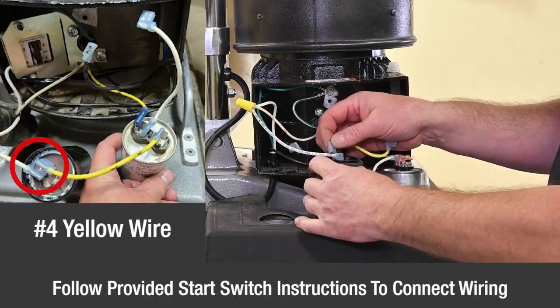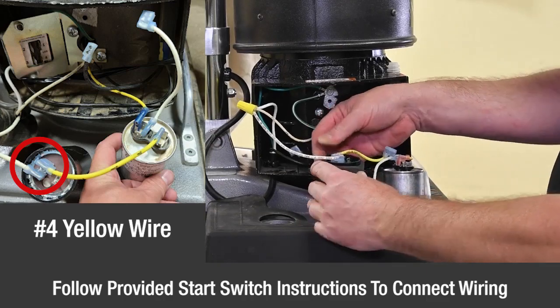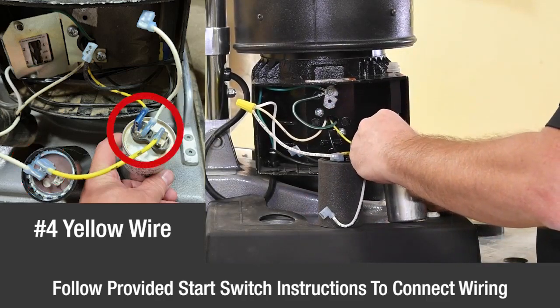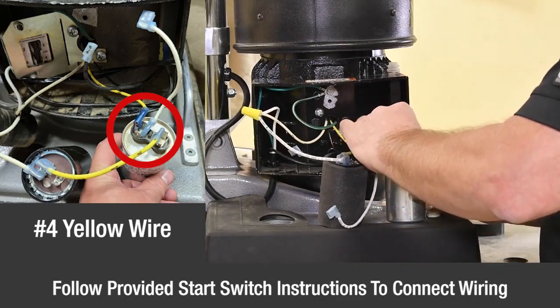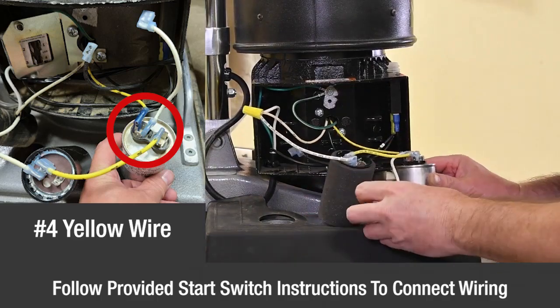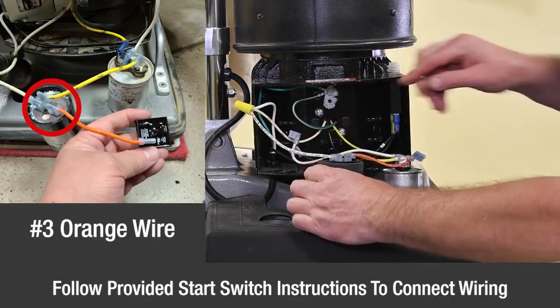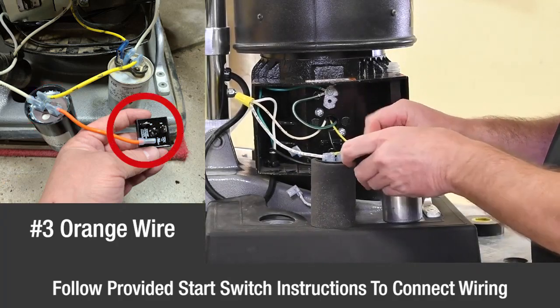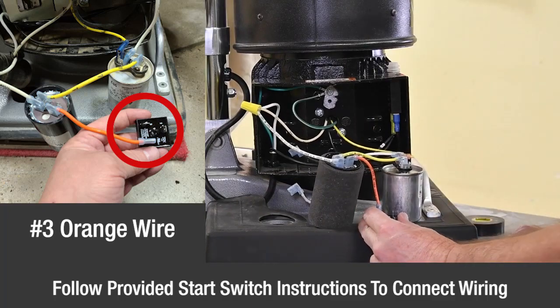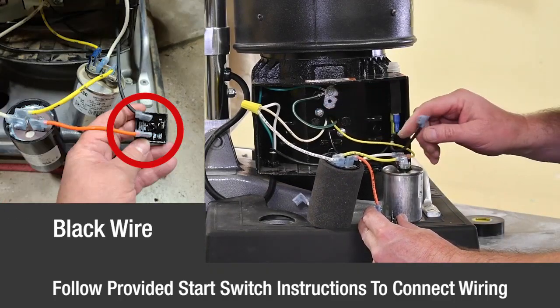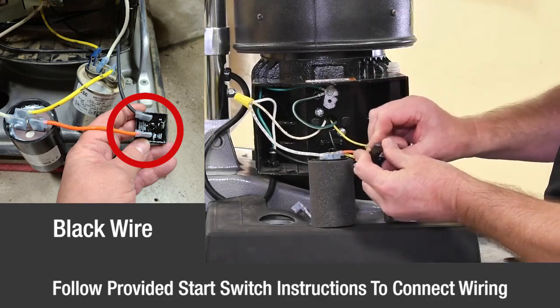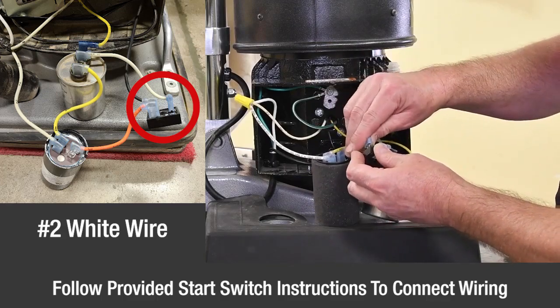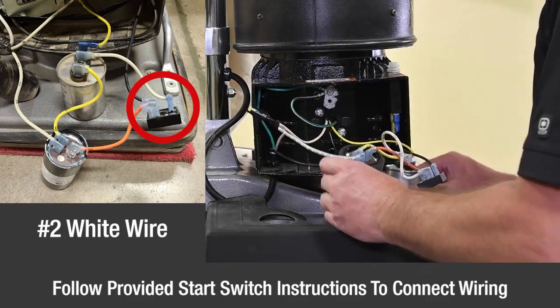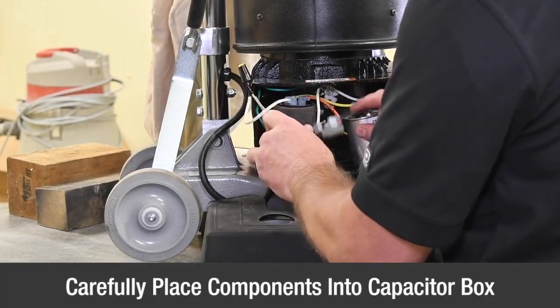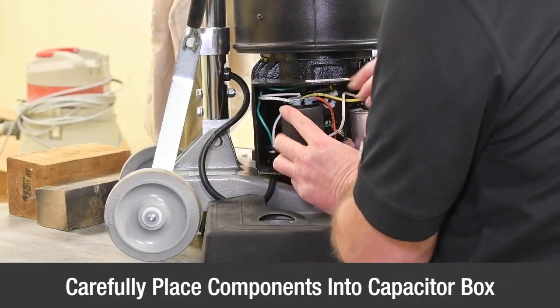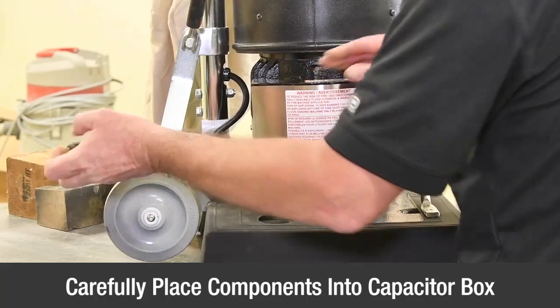Connect one end of one of the previously removed number 4 yellow jumper wires to the start capacitor on the terminal with the white wire. Connect the other end to the open terminal on the run capacitor. Connect one end of the previously removed number 3 orange wire to the open terminal on the new start capacitor. Connect the other end to the number 1 terminal on the new start switch. Connect the black wire from the motor to the number 5 terminal on the new start switch. Connect the number 2 white wire on the run capacitor to the number 2 terminal on the new start switch. Place all the connected components into the capacitor box. Be sure there are no loose or crimped wires and install the capacitor box cover.